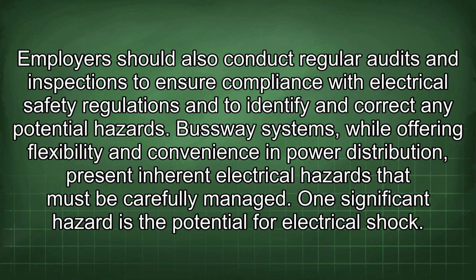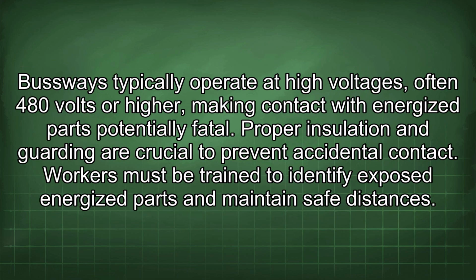Busway systems, while offering flexibility and convenience in power distribution, present inherent electrical hazards that must be carefully managed. One significant hazard is the potential for electrical shock. Busways typically operate at high voltages, often 480 volts or higher, making contact with energized parts potentially fatal. Proper insulation and guarding are crucial to prevent accidental contact.